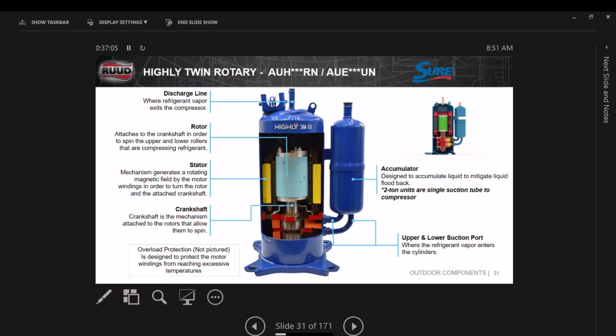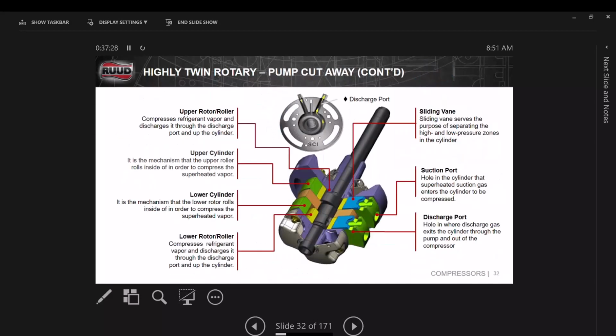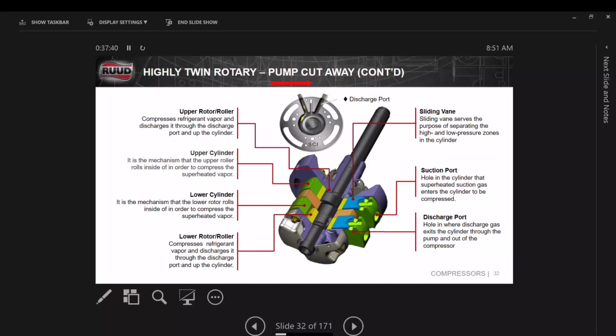And you see the accumulator over here. Each one of these has its own chamber, I guess. There's a vane in the middle of this. So it's basically like two pistons. Yep. Here it is in operation. As you can see, there's the discharge port on the right, the suction port's on the left. And right here in the middle there, you see that little thing going up and down? That's the vane, or the valve, that's going to separate suction from liquid, high side from low side.